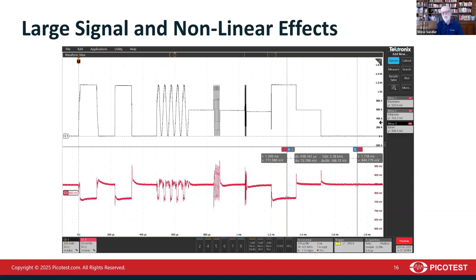Here we can see a better picture of what those responses look like, and we can clearly see the differences between these two steps: same current, really different voltages. This causes us tremendous trouble, because one of the presumptions we've always had in power integrity, in fact the entire basis of power integrity analysis, was the assessment of impedance. We tried to create a finite and fixed target impedance, calculating what the target impedance was, and it's supposed to be flat. But here's the thing: if we had a fixed impedance and generated a fixed current, we would get a fixed response. That would mean each of these two responses would have to look identical, because we had the same DI and theoretically the same impedance. But these don't look the same.